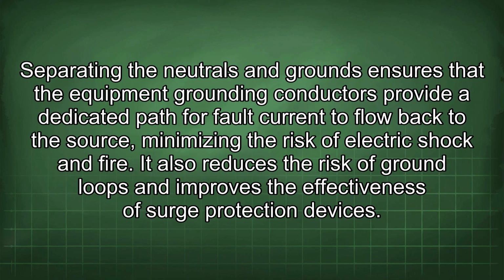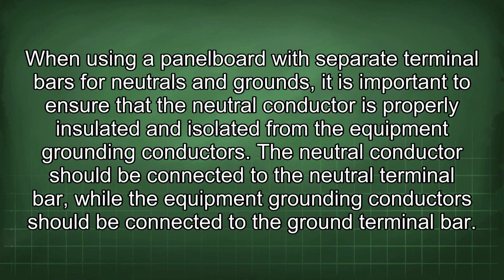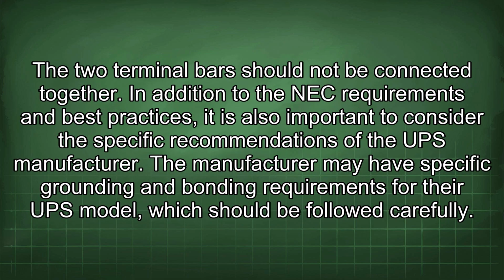Separating the neutrals and grounds ensures that the equipment grounding conductors provide a dedicated path for fault current to flow back to the source, minimizing the risk of electric shock and fire. It also reduces the risk of ground loops and improves the effectiveness of surge protection devices. When using a panel board with separate terminal bars for neutrals and grounds, it is important to ensure that the neutral conductor is properly insulated and isolated from the equipment grounding conductors. The neutral conductor should be connected to the neutral terminal bar, while the equipment grounding conductors should be connected to the ground terminal bar. The two terminal bars should not be connected together.